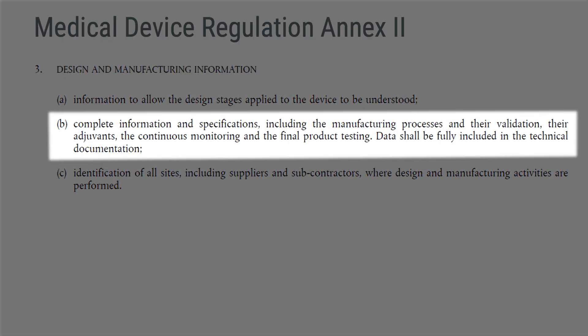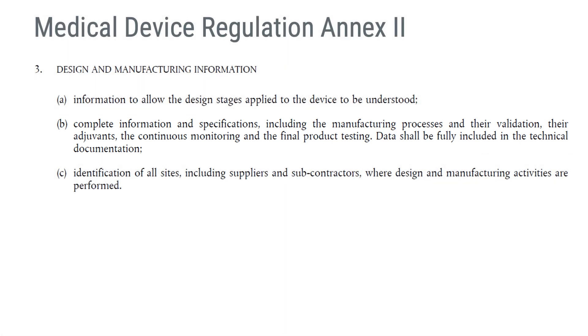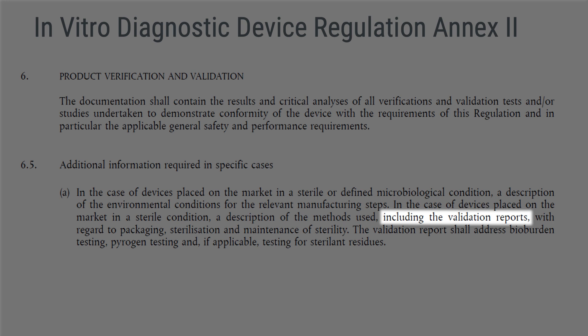MDR Annex 2.3b states that manufacturers shall have complete information on manufacturing processes and their validation. In IVDR Annex 2.6.5a, it is pointed out that process validation needs to be performed for devices that are placed on the market in sterile or defined microbial conditions. So 21 CFR Part 820, the MDR, and the IVDR are regulations that medical device manufacturers selling to the US and EU markets must comply with. These regulations cover all medical devices and span over the entire life cycle of the medical device.